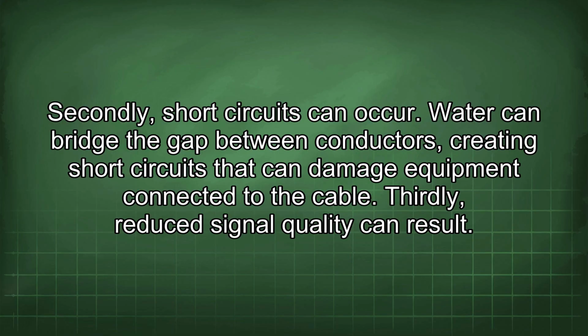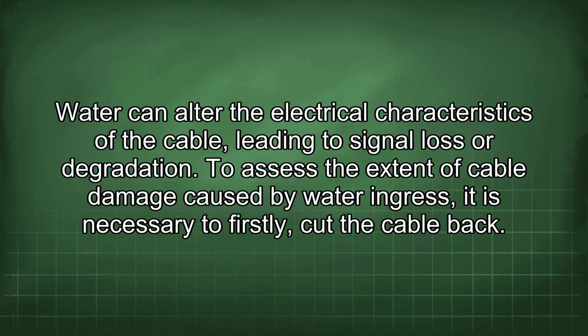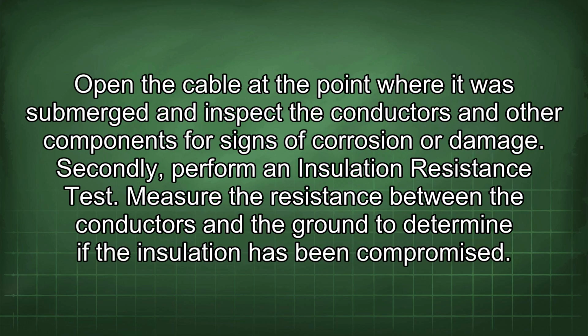Thirdly, reduced signal quality can result. Water can alter the electrical characteristics of the cable, leading to signal loss or degradation. To assess the extent of cable damage caused by water ingress, it is necessary to firstly cut the cable back. Open the cable at the point where it was submerged and inspect the conductors and other components for signs of corrosion or damage. Secondly, perform an insulation resistance test. Measure the resistance between the conductors and the ground to determine if the insulation has been compromised.